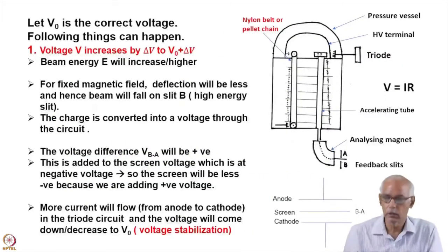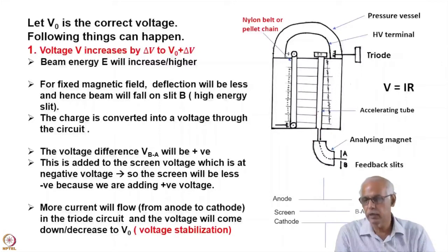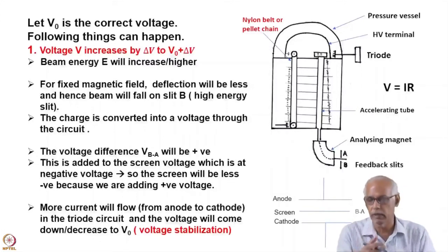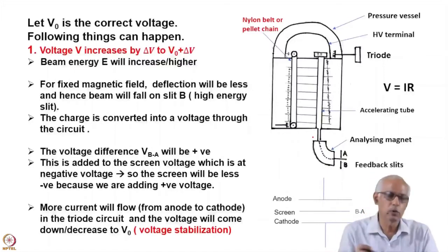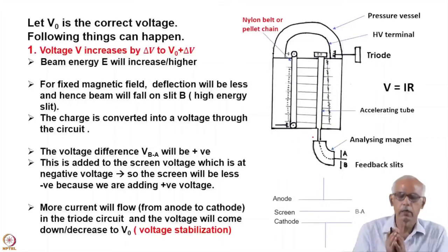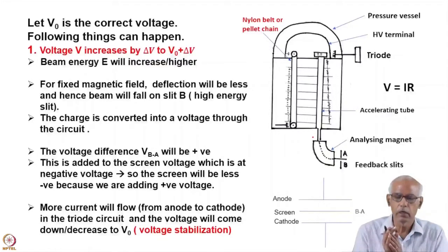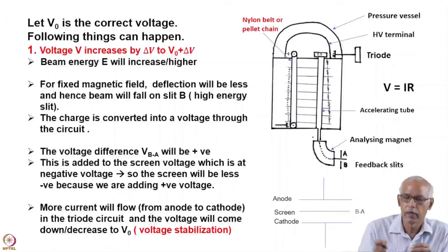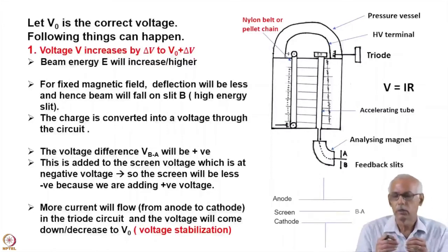The beam is accelerated and analyzed for energy. The magnetic field is set up in the analyzing magnet corresponding to a particular energy, and that energy depends on the voltage. If there is a variation in the voltage, the energy will change. Suppose voltage V0 is the correct voltage. If the voltage V increases by delta V, meaning the actual voltage has become V0 plus delta V, then once the voltage has increased, beam energy will also increase.